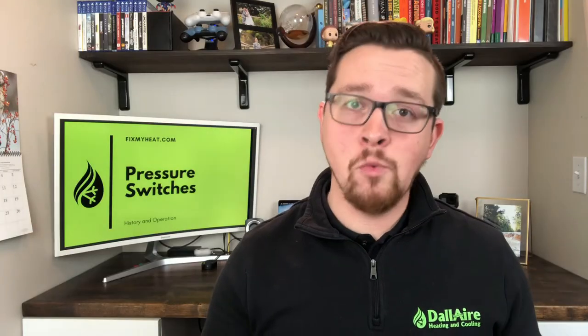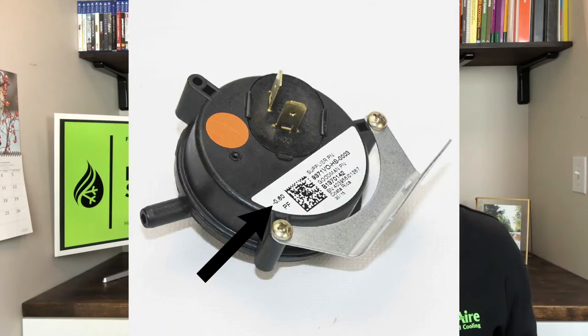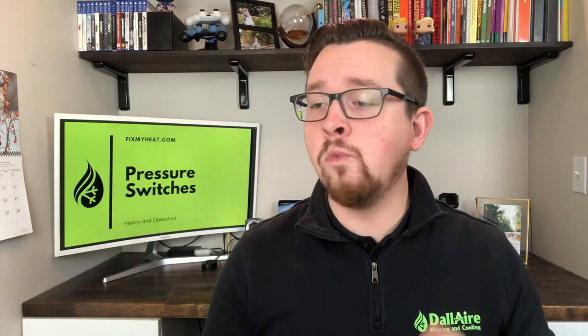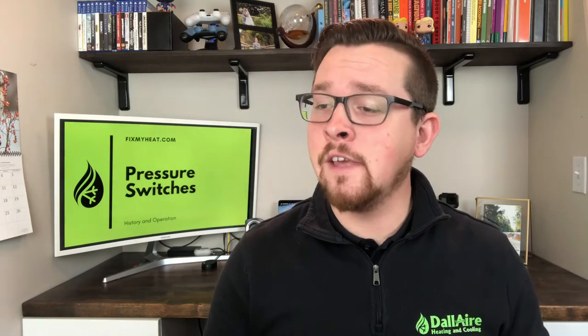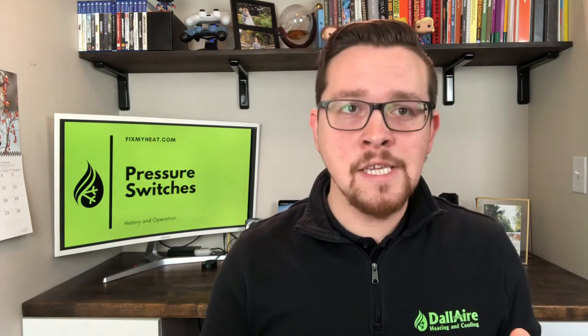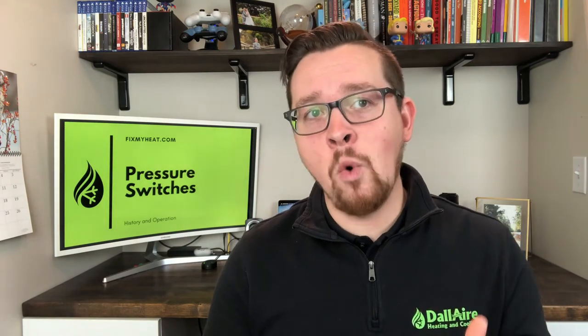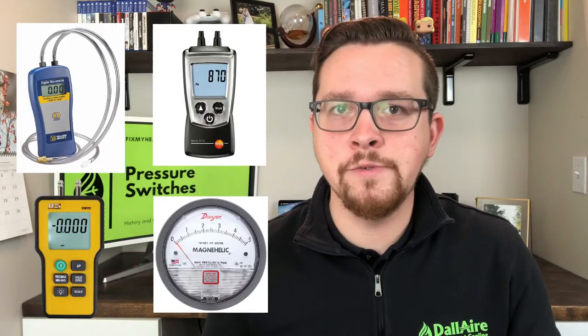The pressure switch should have a rating on it, normally measured in inches of water column. Inches of water column is defined as the pressure exerted by a column of water of 1 inch in height at defined conditions. It's literally the amount of pressure that it takes to move a column of water 1 inch. And this is the tool used to measure that. Well, one of the tools you can use.